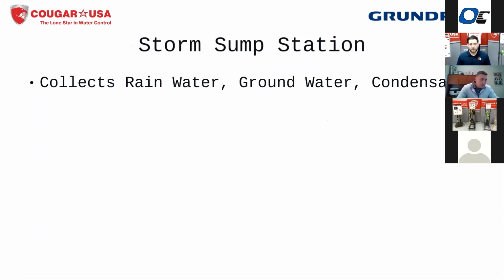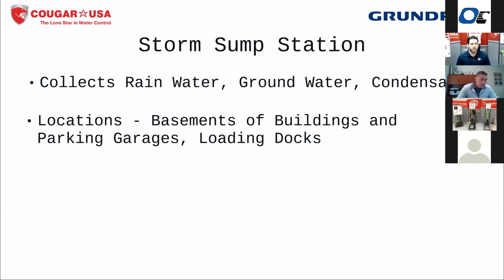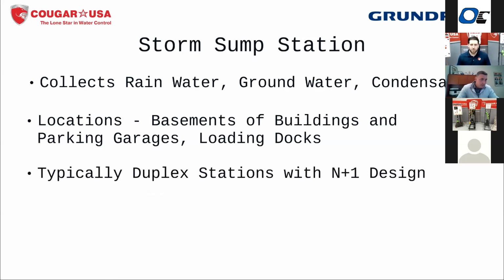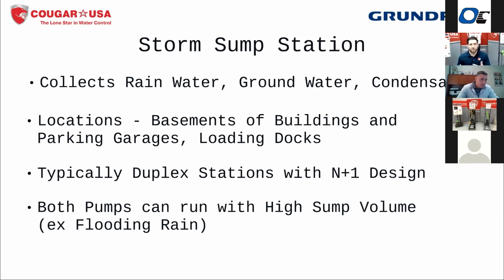Okay. So when we're looking at sump stations for the storm, it's going to be anything: rainwater, groundwater, maybe condensate from your HVAC system if you're not recovering that, all going into these, quote unquote, cleaner basins there. You're going to see them in basements, parking garages, loading docks, things of that nature. And we're always going to want at least a duplex station on these with that N+1 design, meaning each one of the pumps can handle the full load of the system in case one of the pumps fails. But with a storm station, especially here in South Texas, where we have these major hurricane and flooding events, it might be typical to see both pumps run in a storm station.